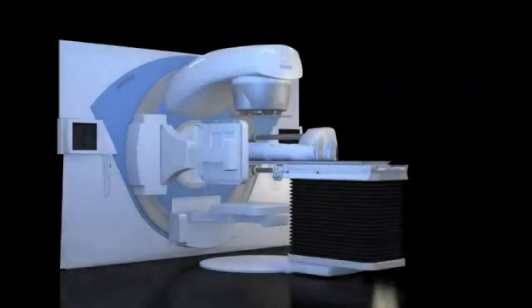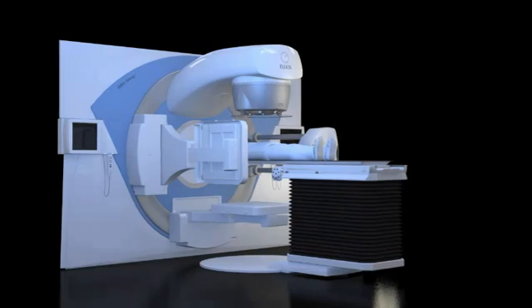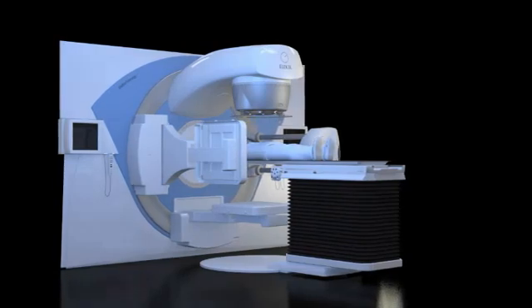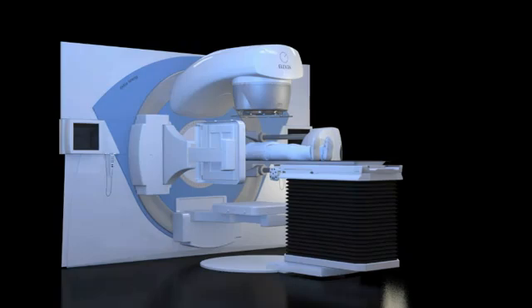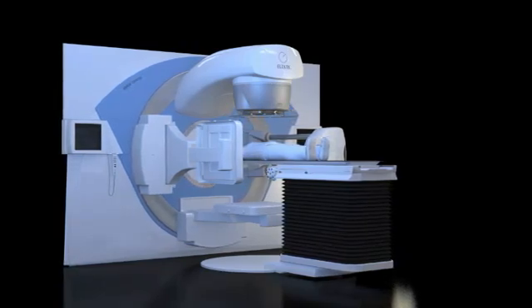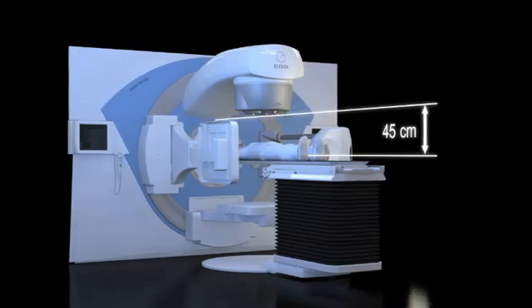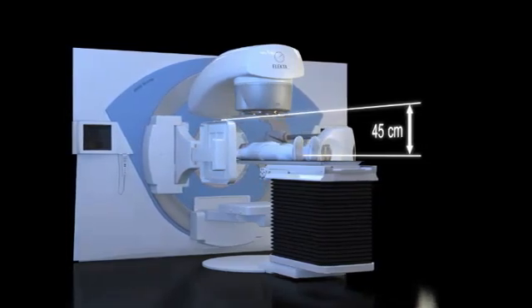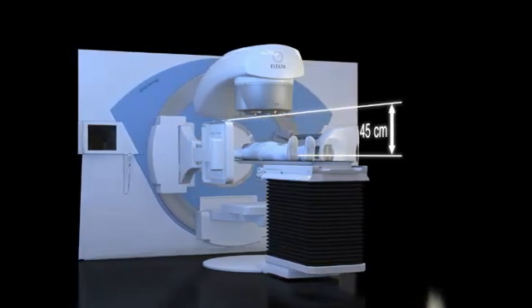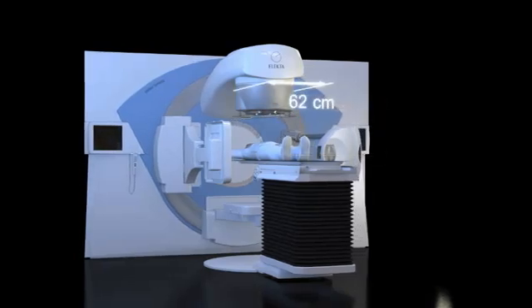Clearance. Clearance is the free space available under the LINAC for patient treatment and it varies with different protocols and fixation devices. It is a combination of the distance between the lower surface of the radiation head and the isocenter, 45 cm, and the head diameter, 62 cm.